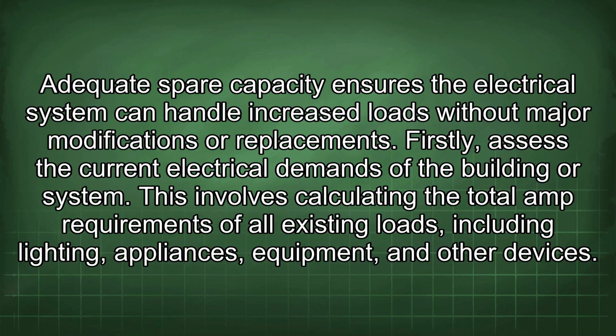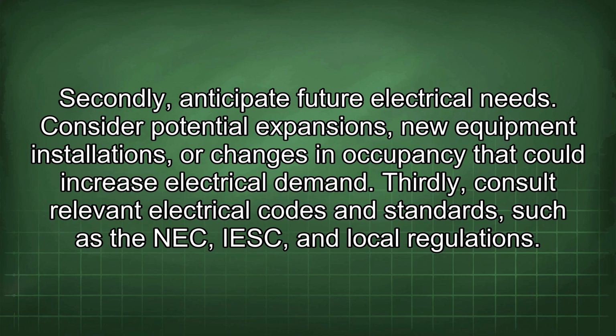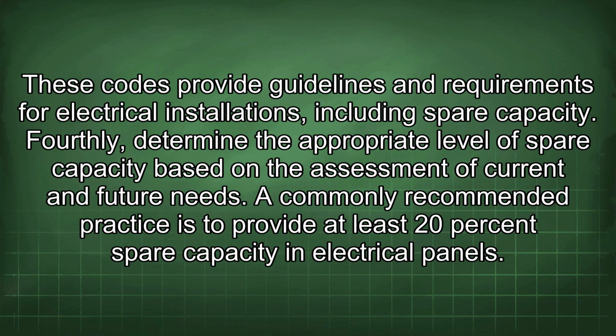Firstly, assess the current electrical demands of the building or system. This involves calculating the total amp requirements of all existing loads, including lighting, appliances, equipment, and other devices. Secondly, anticipate future electrical needs. Consider potential expansions, new equipment installations, or changes in occupancy that could increase electrical demand. Thirdly, consult relevant electrical codes and standards such as the NEC, IESC, and local regulations. These codes provide guidelines and requirements for electrical installations, including spare capacity.